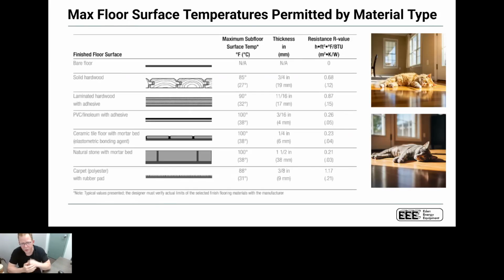It's not a lot of heat that we need to get into that space. So we need to really understand that. And the other thing I really like to point out too is that air to waters are really designed well to deliver that 100-degree water into the floor to try to heat the space. And you will occasionally run into this, and I like to always have a slide anytime I'm talking about hydronics, where sometimes people get freaked out going, hydronic heating, it can be really hard on hardwood floors and it's going to cause problems. It's just not that worth the headache.